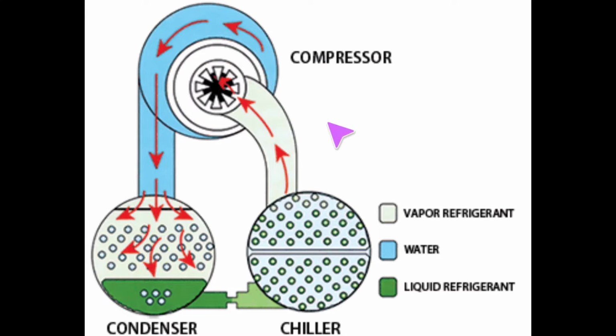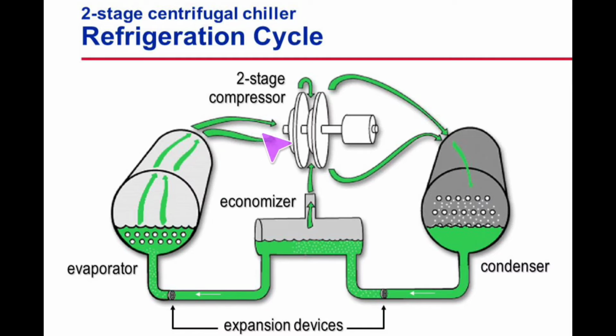I'm not going to spend a whole lot of time on this. They function off the same basic design principles every machine runs from. But again, it's just some sort of visualization that might help with the rest of this process. From here, this is our suction line coming in. Okay, so from that other example, we're going to talk a little deeper into the actual cycle of the system at this point. So this is your evaporator. We're pulling through the suction volute, through the guide vanes.